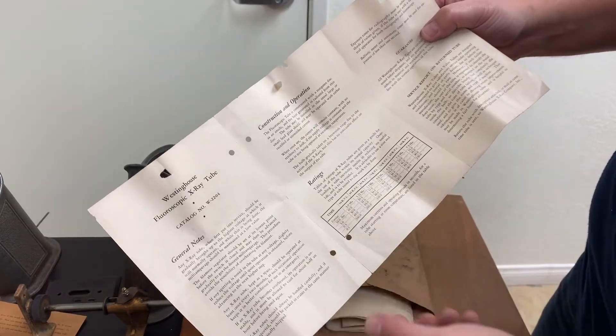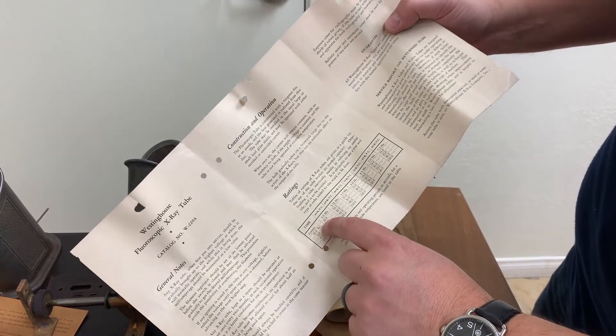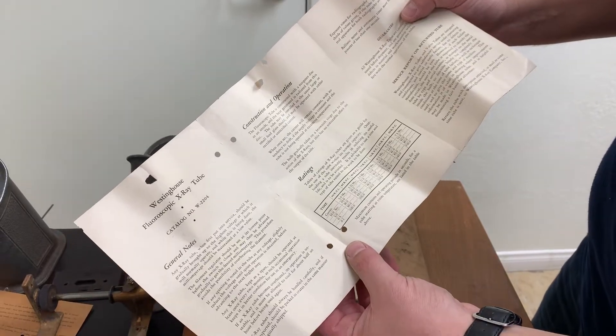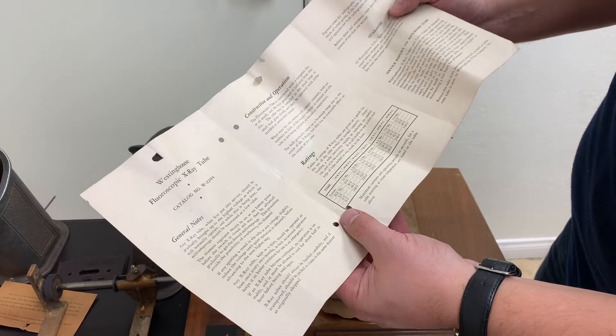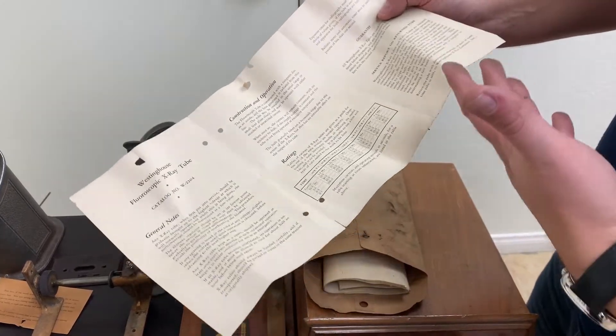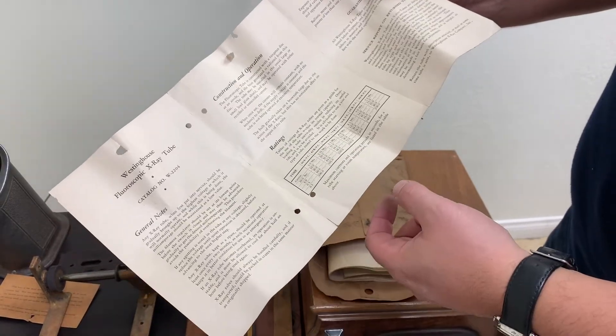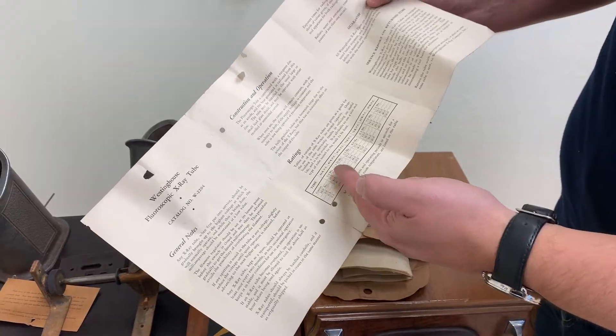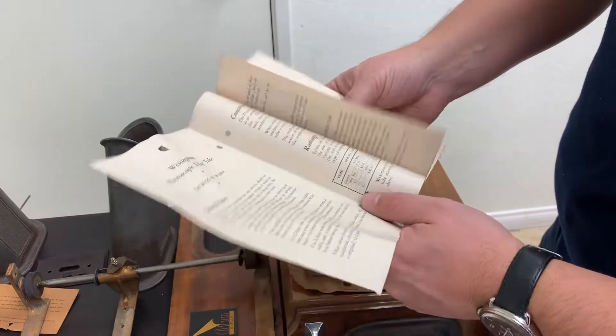But these machines were typically used by pushing a button and looking at the image for a while — 10 seconds is more typical of the operation. So again, a lot of power. We're talking about 450 watts on the x-ray source. In our machines, a typical 90 kV source operates at 8 watts, which is a fraction of this 450 watts. And our systems have a lot of lead shielding.